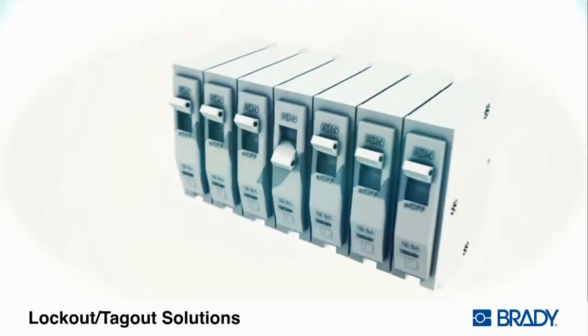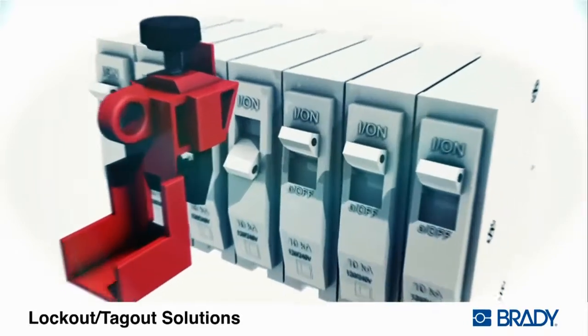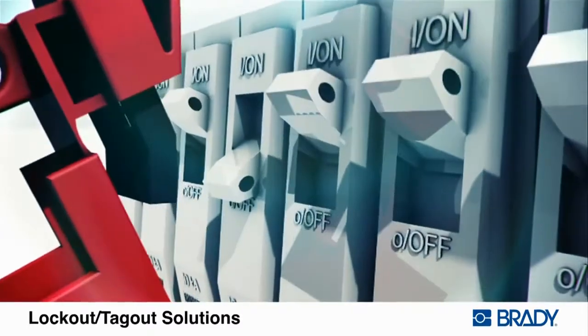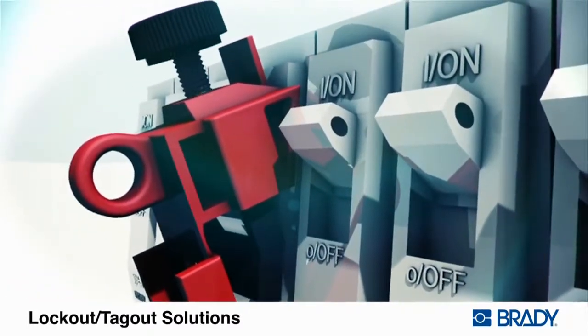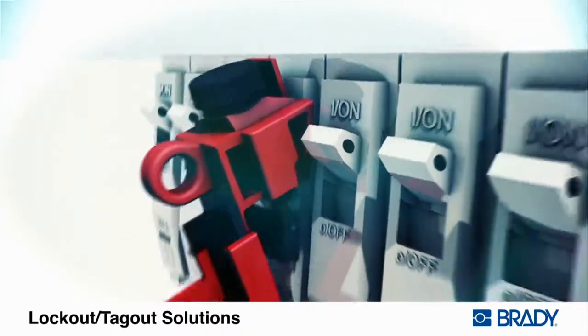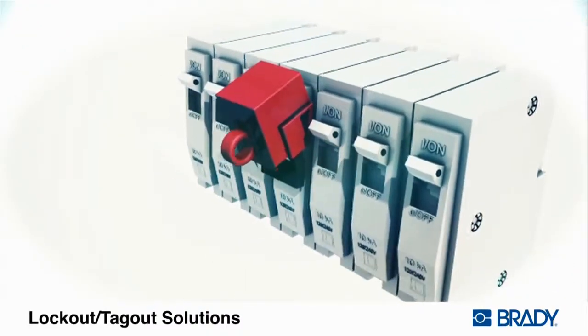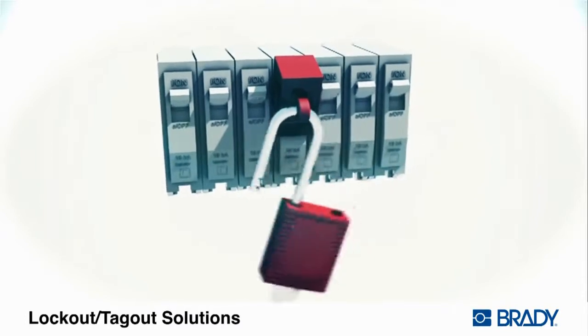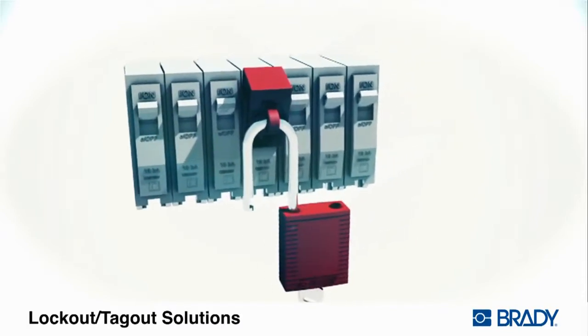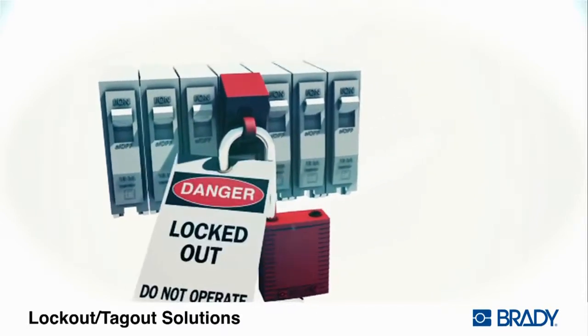Put the circuit breaker in the off position and place the lockout device over the circuit breaker switch tongue. Rotate the thumb wheel clockwise to secure the lockout device. Attach the padlock and worker's protective tag. This device is available in 3 sizes to accommodate a variety of circuit breakers.